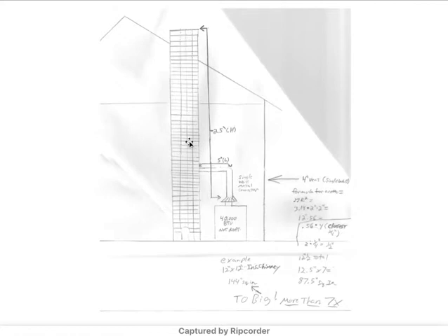You have to run a chimney liner down here. All right. A lot of guys will rip out a boiler right here. That boiler was keeping this chimney nice and warm in the winter when it's cold out. It doesn't have that anymore. So when this water heater fires off, the flue's not making it all the way up because it's not hot enough. And that's why they got real strict on the chimneys that were on the outside of the house. But now they want you to do it to all of them. And it makes sense. And it's probably a good rule.